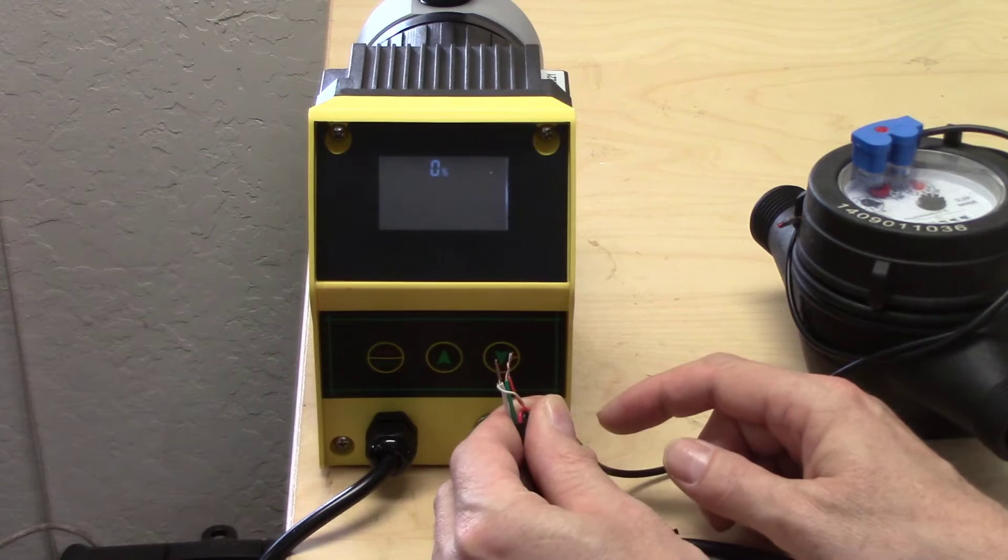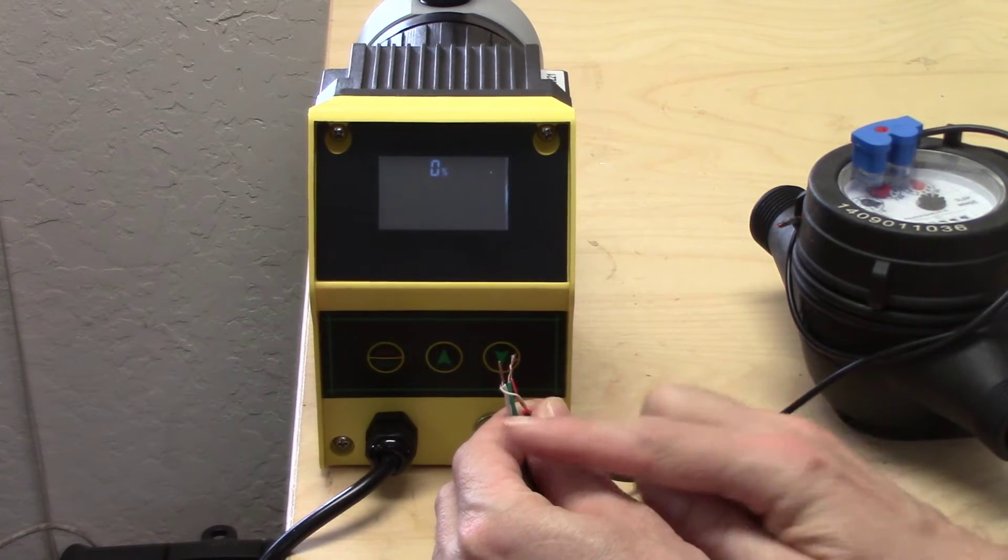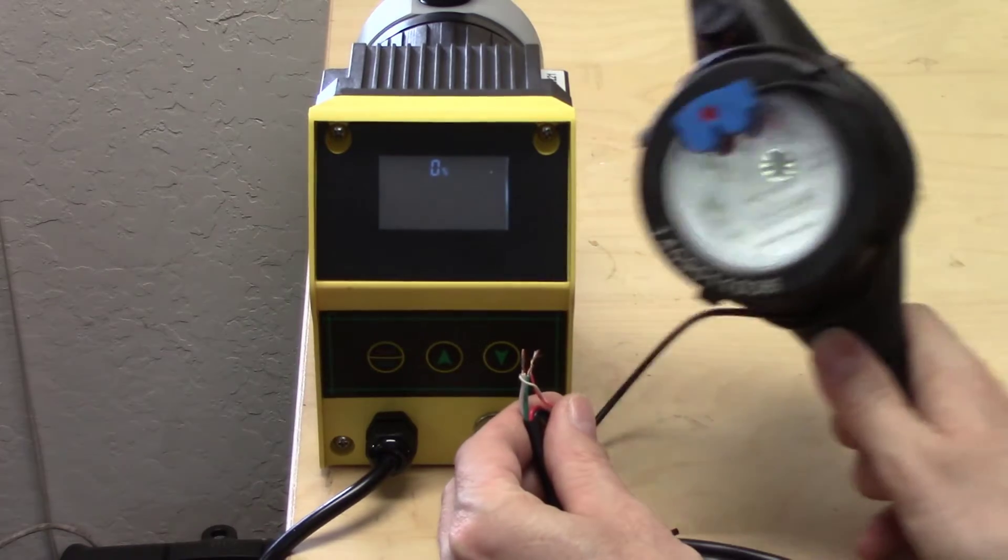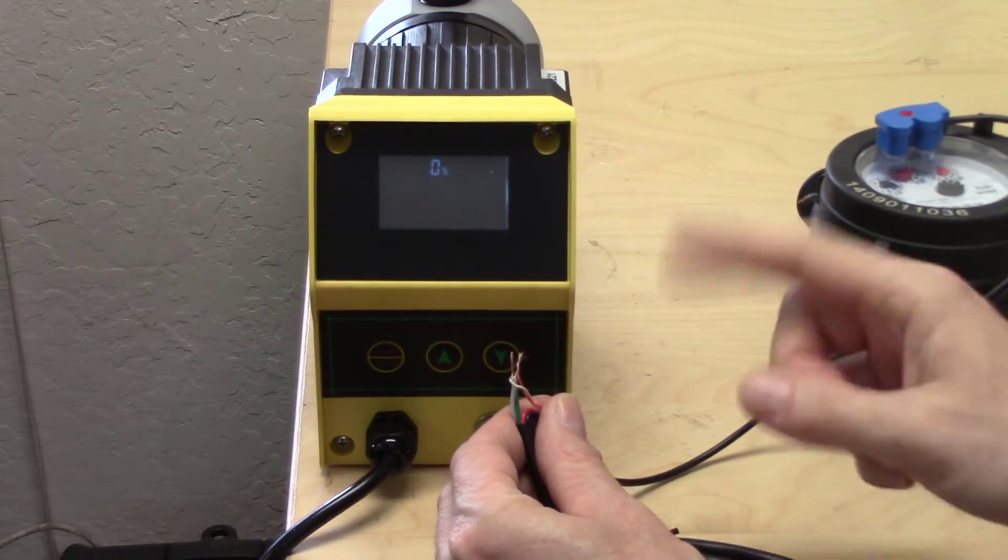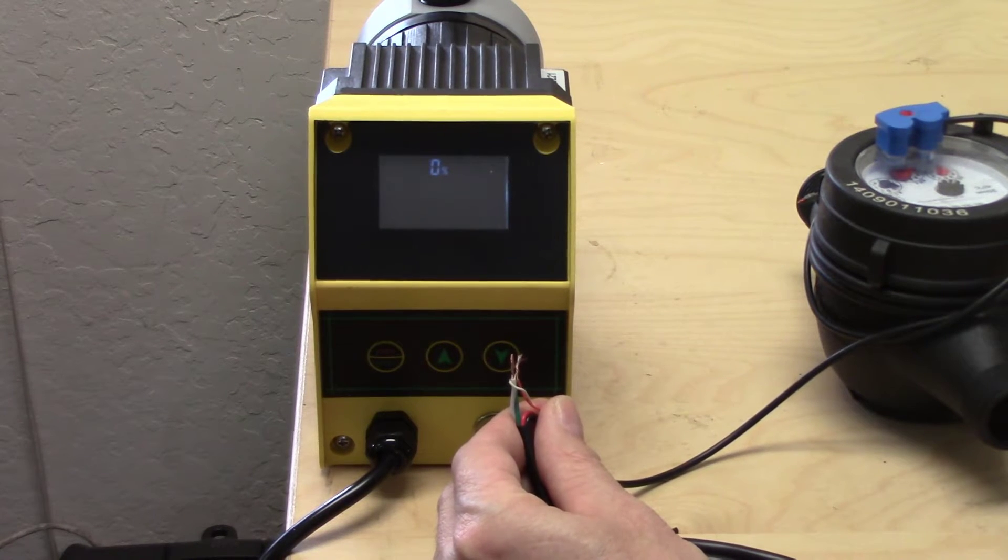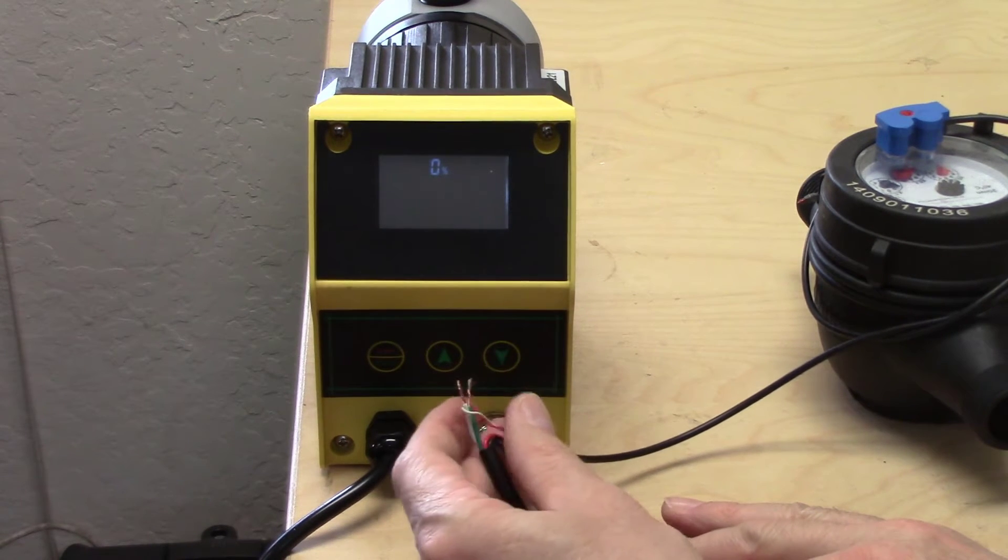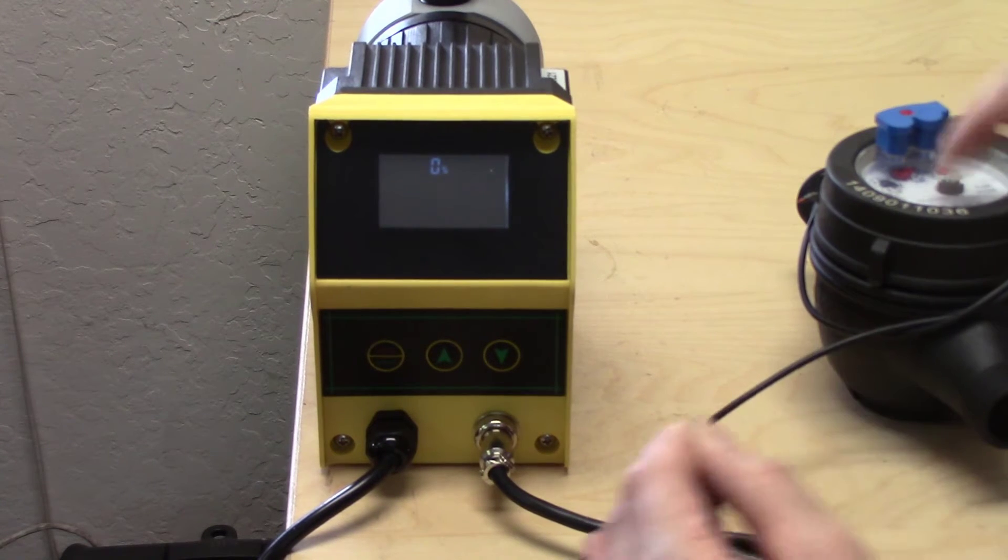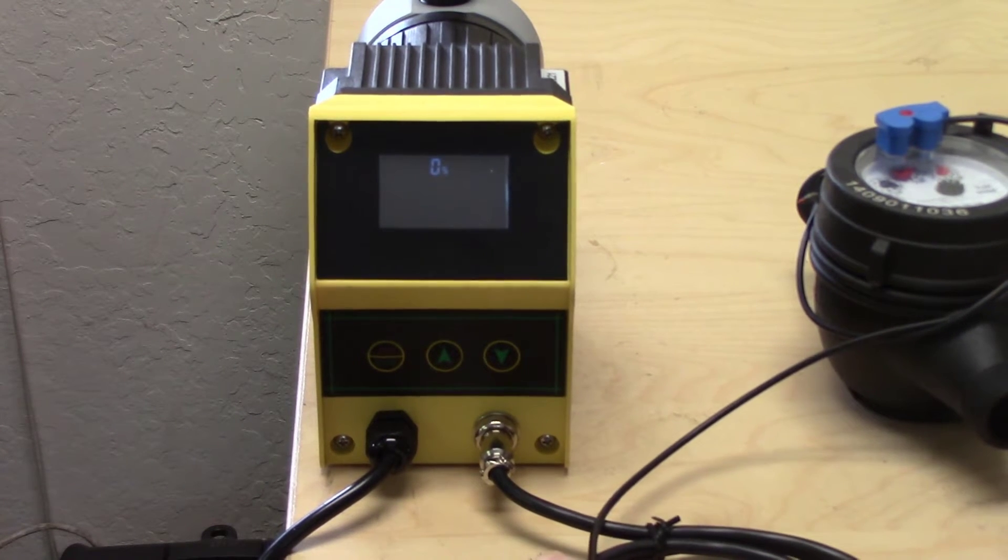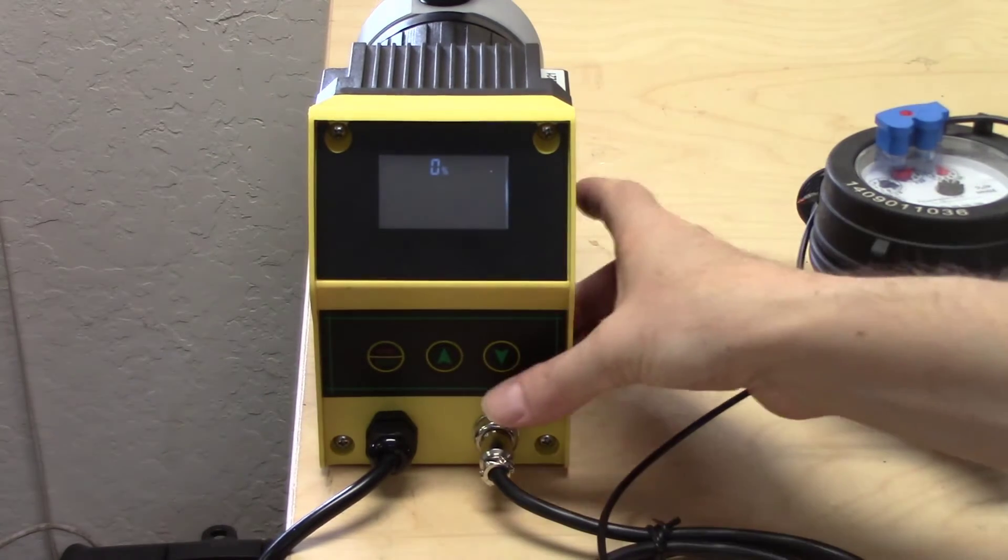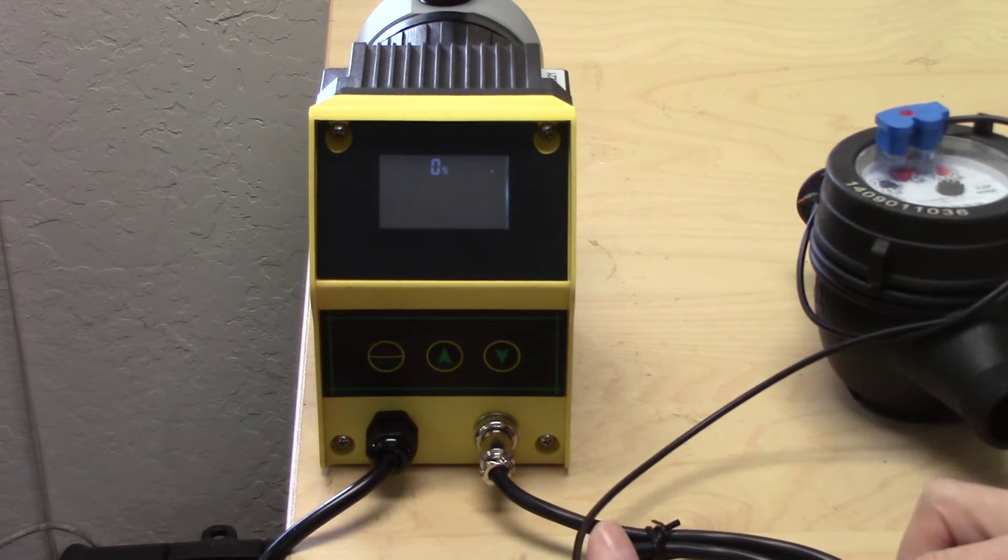That is the white common wire. White goes to white, and red from the flow meter goes to the green wire on the cable from the Precision Digital. So it goes white to white and red to green. When you have those hooked up, when a gallon of water flows through the meter, it will send a pulse and that will trigger the pump to pulse and squirt chlorine however many times per gallon that you choose.